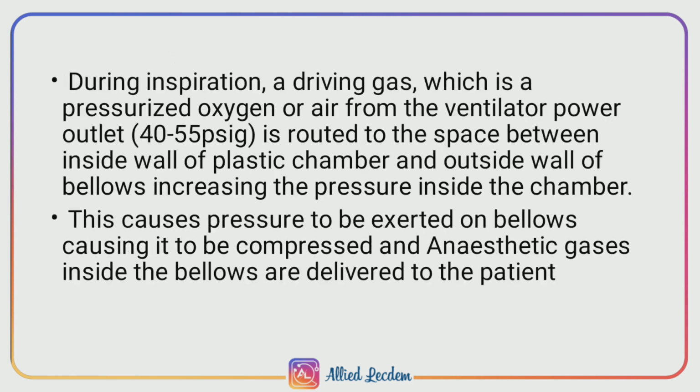During inspiration, the driving gas, which is pressurized O2 and air, is routed towards the space between the plastic chamber and the bellows, which is the outside space of the bellows, thereby increasing the pressure inside the whole canister or chamber. This increasing pressure will cause the bellows to be compressed, and the anesthetic gas inside the bellows will be delivered to the patient.